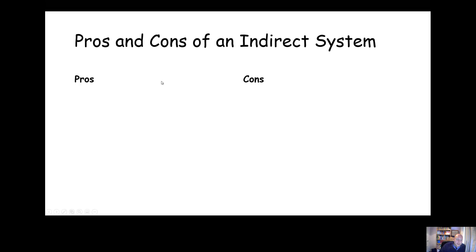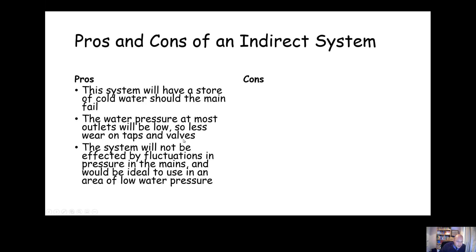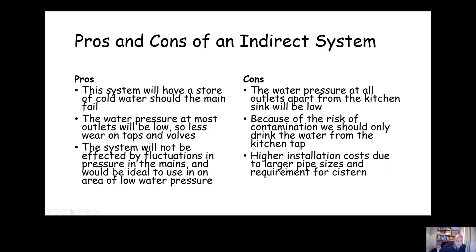The pros and cons of an indirect system are basically the reverse. Pros: there is a store of cold water should the mains fail. Water pressure at most outlets is low, so there's less wear on taps and valves, and the system is unaffected by pressure fluctuations — ideal in areas of low mains pressure. Cons: water pressure at all outlets apart from the kitchen sink will be low. Due to contamination risk, drinking water is only available from the kitchen tap. Higher installation costs due to larger pipe sizes and the space requirement for the cistern in the attic.